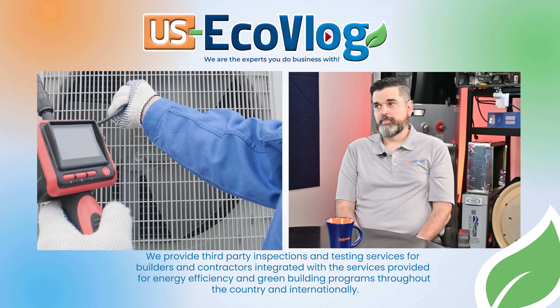We also do a watt draw to make sure the air handler isn't using too much or too little wattage. The fifth item would be the refrigerant charge. We can't do that check ourselves, so we have the HVAC installer send us their weigh-in proof that the refrigerant was put in the correct amount.